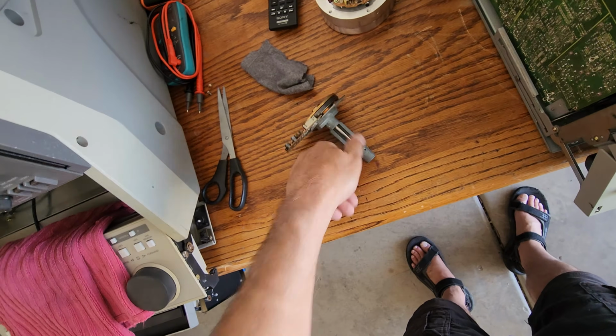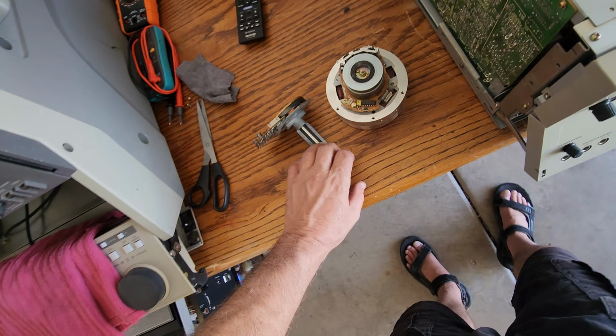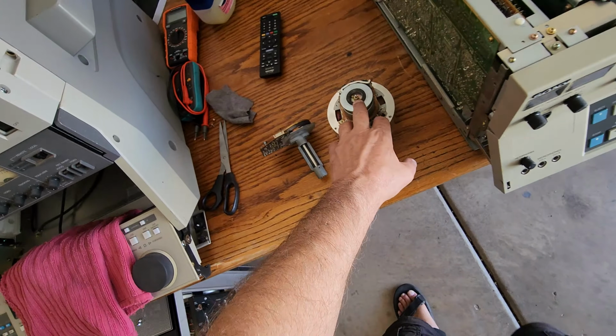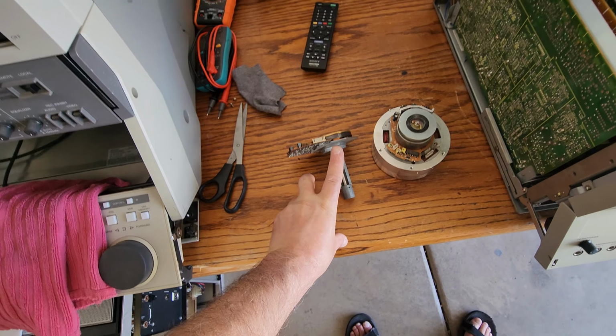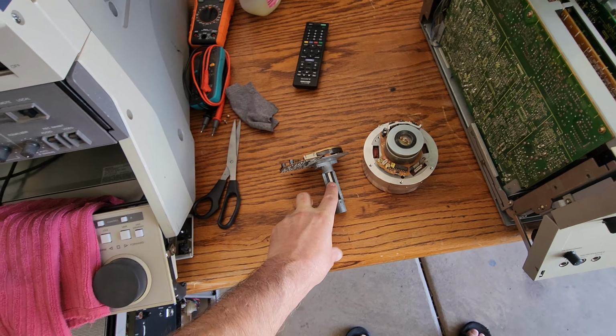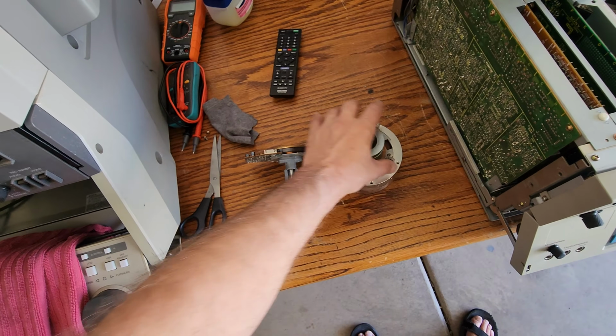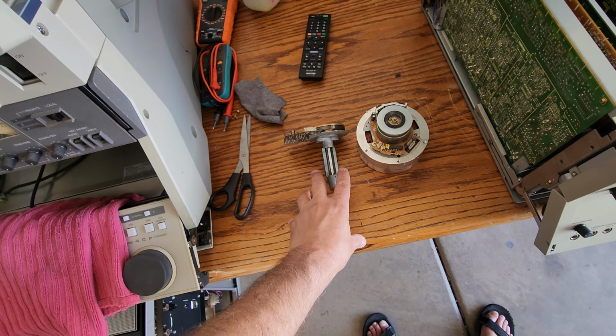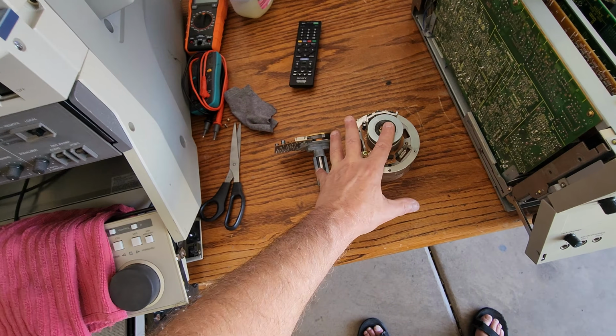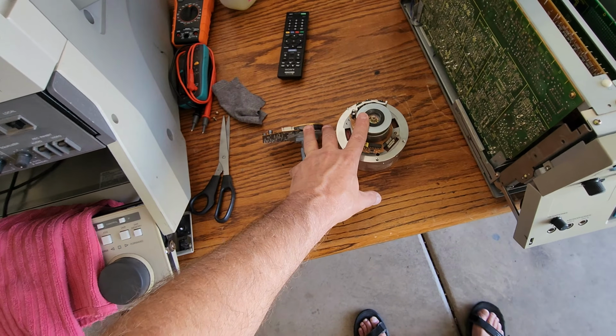So this thing had 2 failures. It had the entire scanner failure and the entire capstan motor failure. Both of these are shot. I did test them both to make sure I was correct, and they are. Both of these units are completely shot.